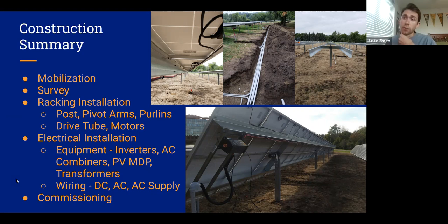So that's what the racking system might look like. Then you get into the electrical installation, which you see on the top left and middle. You can see the string wiring coming along the purlins, which run back to the inverters, and the trenches dug to run the conductors. We typically have a trench line that takes all the conductors to the inverters, then to the combiners, to the main distribution panel, to the transformers, as seen there.